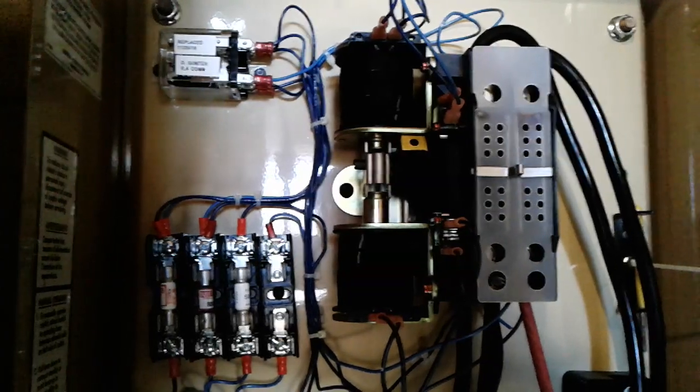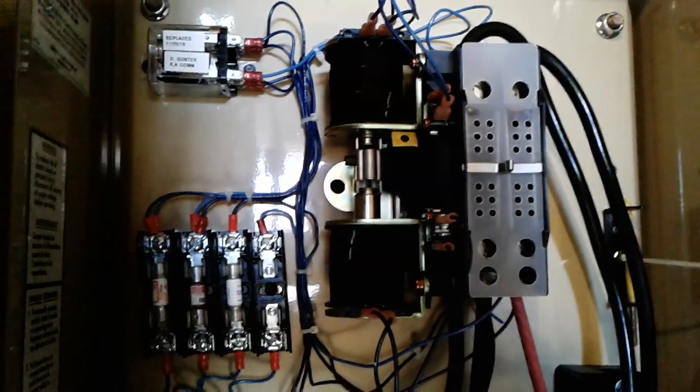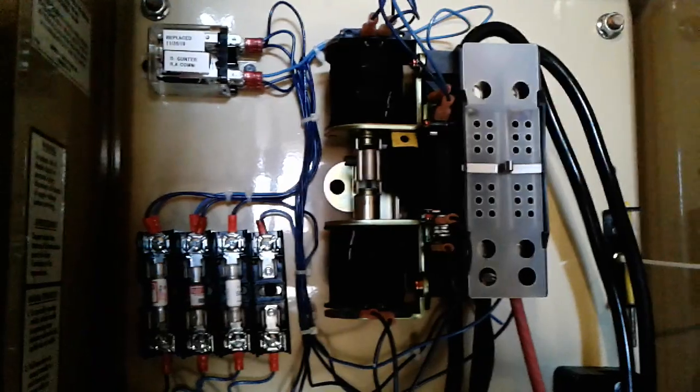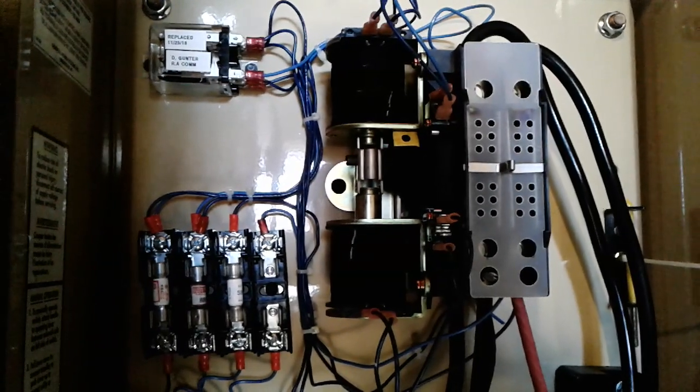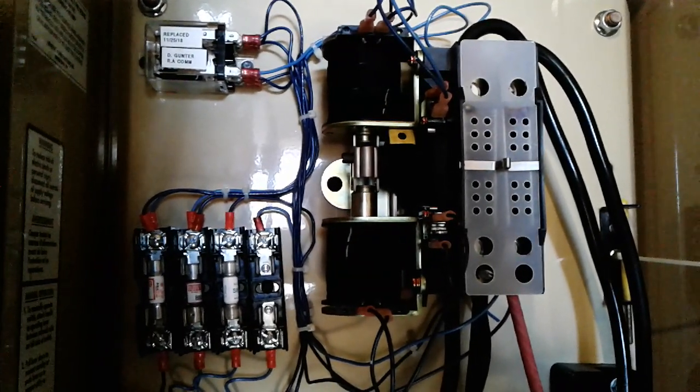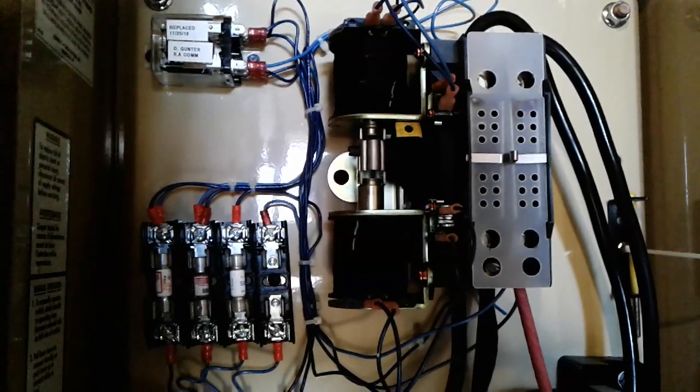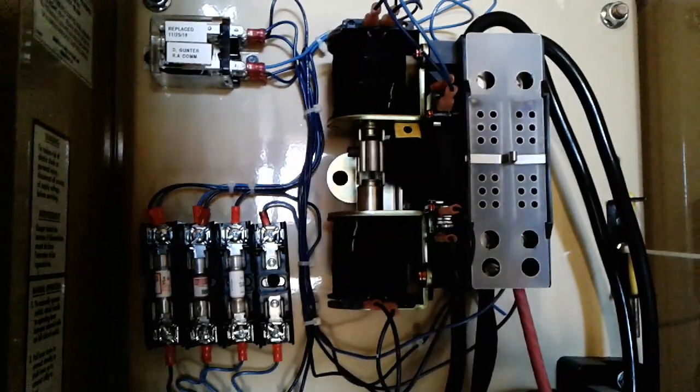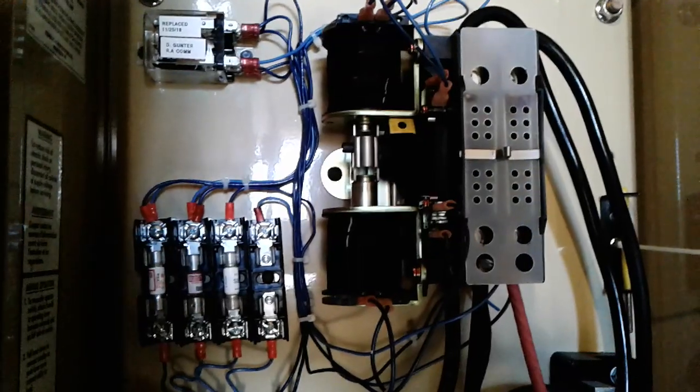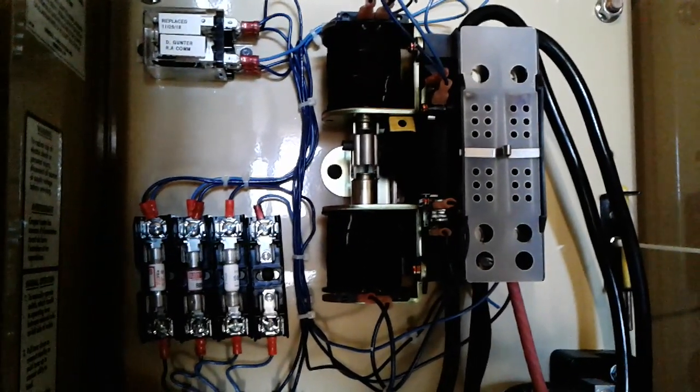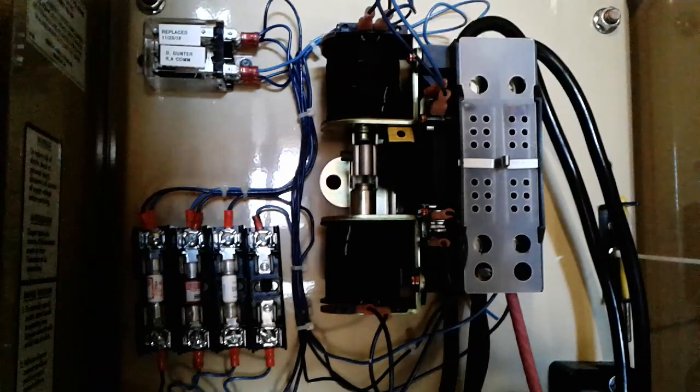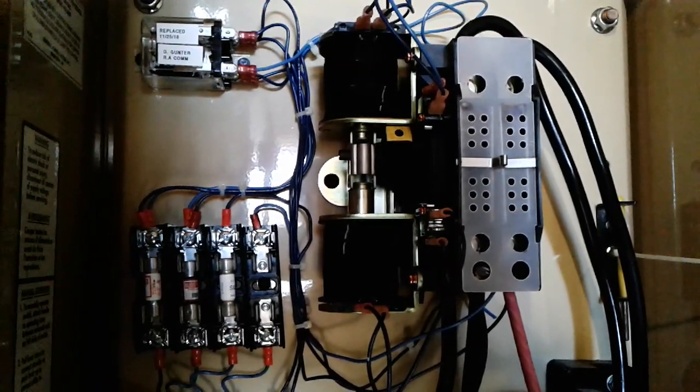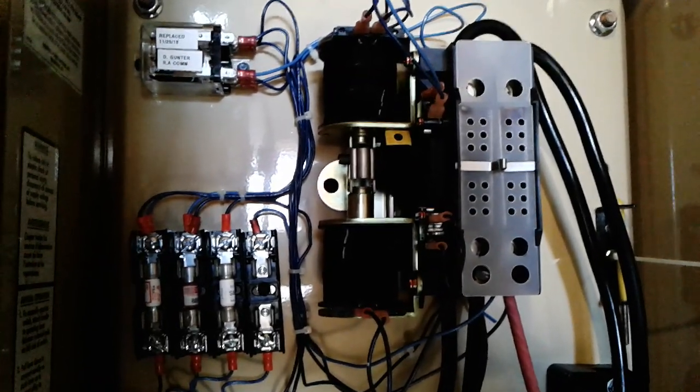The generator should be getting pretty close to shutting itself down. It runs for a little while to keep its speed, its RPMs, its voltage up, in case it's one of those cases where the AC utilities are flickering on and off, so the generator is not off-on-off-on. There we go, generator's back in standby, ready to go.